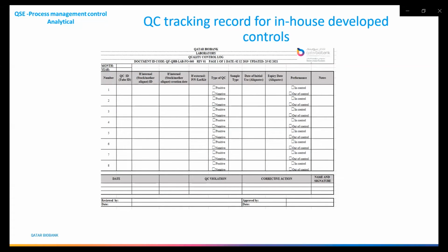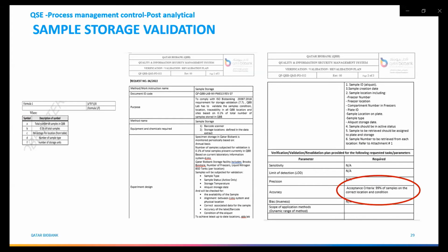Once we have developed our internal QC or purchased an external QC, it's very important to keep track and keep a log of the sample types, when we start to use it, and what the expiry date is, and if there is any QC violation, to document it, and of course to perform a corrective action after that.